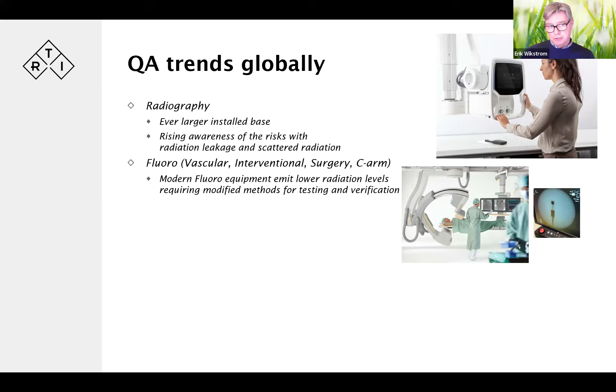For fluoro, we see advancements into more complex systems, with lower doses, but the pulses in the pulsed fluoro, for instance, are getting shorter. That means that the amplitude gets a little bit higher. The dose rate increases. So for that, we also need to keep track of not just the numbers of the dose, but how the dose is produced. That's also something we need to look at, and where the interest is growing.